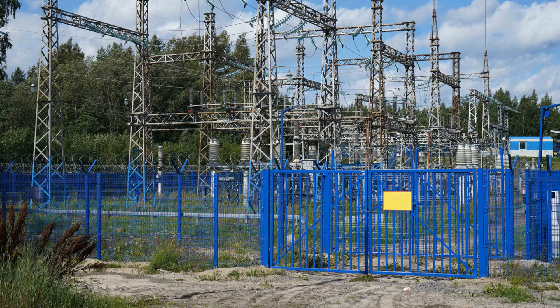The grid's thermal ceiling is not in the transmission lines, though those have their own thermal limits. It is in the power electronics, the switching devices, inverters, and converters that condition and route electricity at every node between generation and consumption. Every large-scale solar installation interfaces with the grid through a DC to AC inverter. Every wind farm uses a back-to-back frequency converter. Every grid-scale battery storage system uses a bidirectional power converter. Every EV fast charging station uses a high-power rectifier and a DC to DC converter.